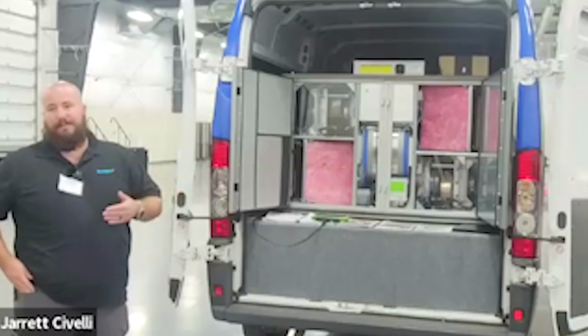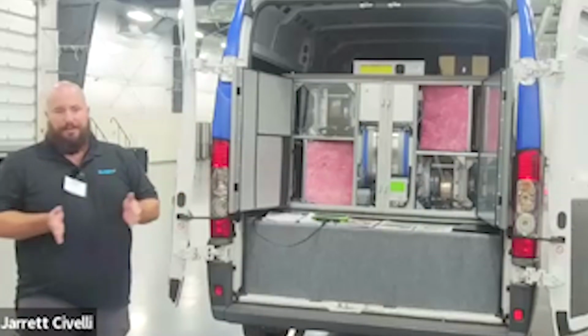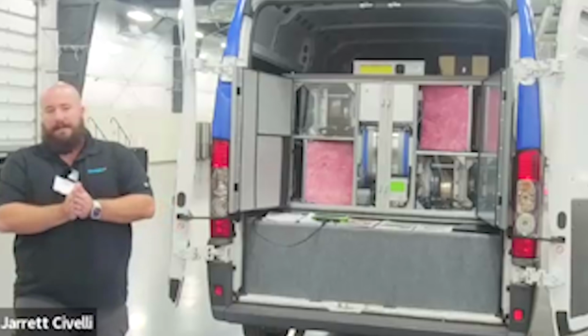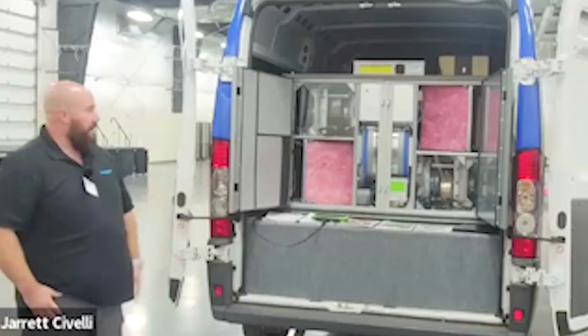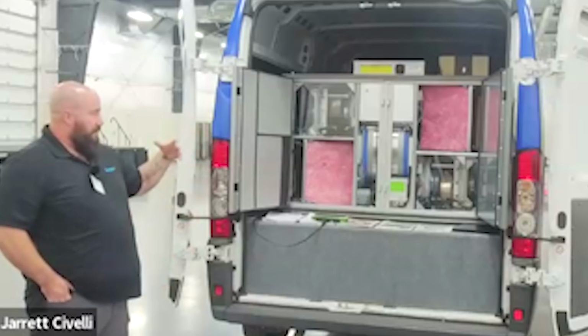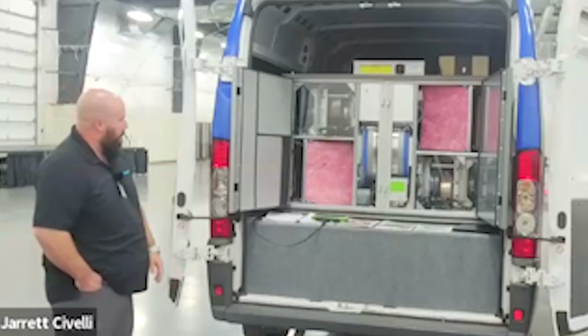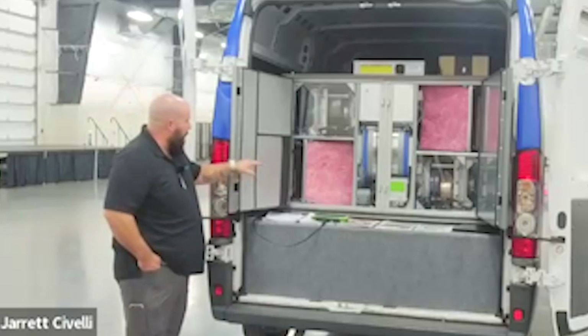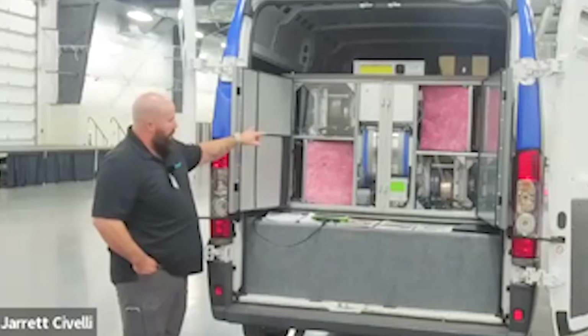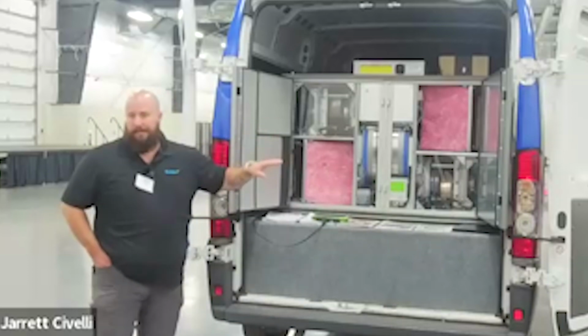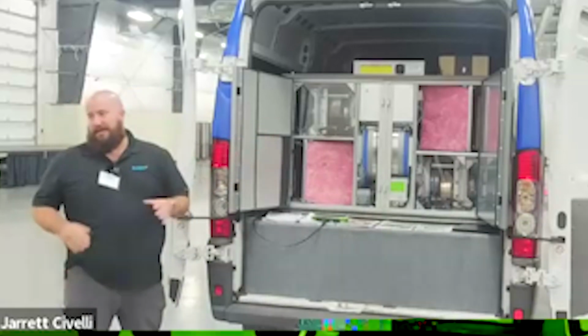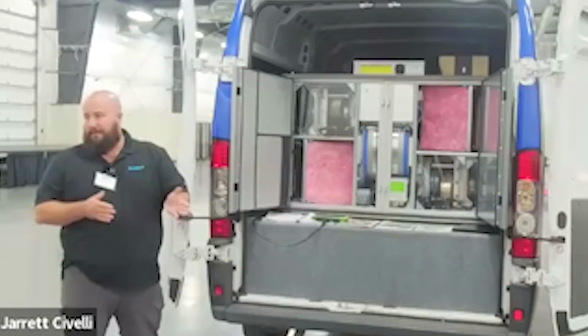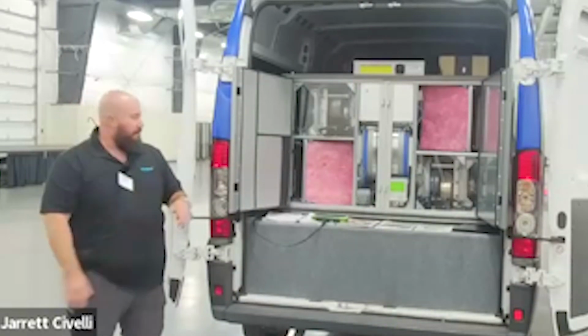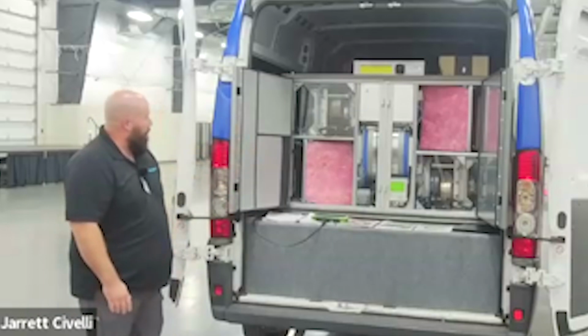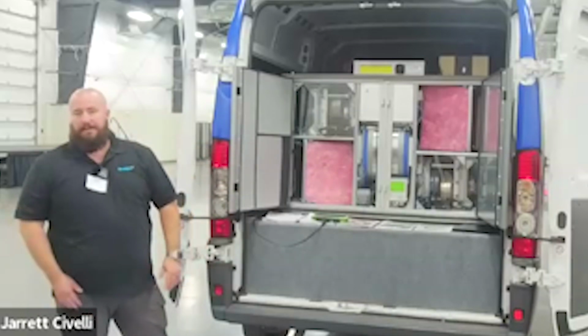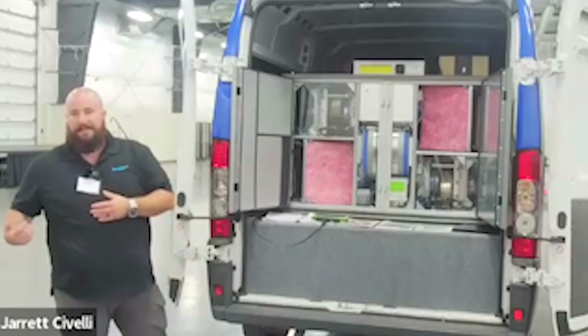The unit itself is made for single-sided access, so you can push it up against a wall, fit it in a closet. That's pretty standard. All of the service is done from the front here. On the service side of things, both of the fans are interchangeable. So the way it's wired and configured, the wiring harness itself is what tells it which position the fan is in. The fans come out pretty quick with a crescent wrench and some wing nuts. So you just loosen a couple things, the whole fan slides out.